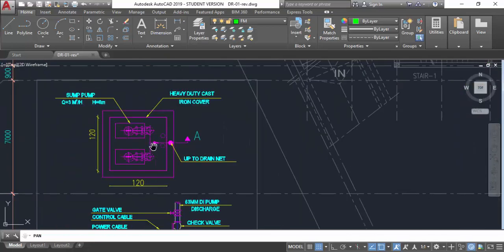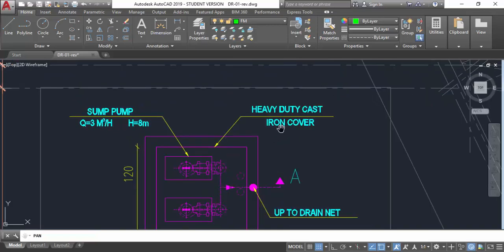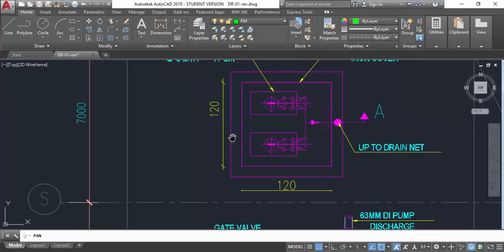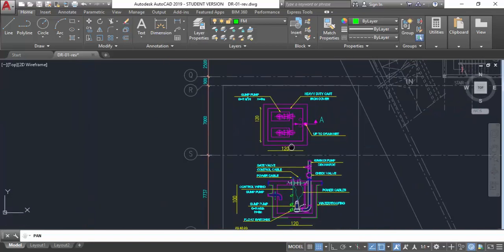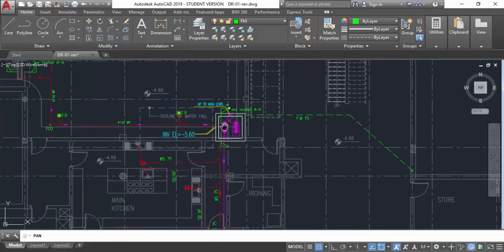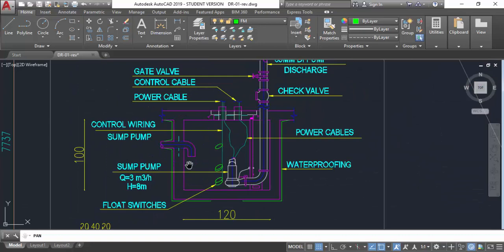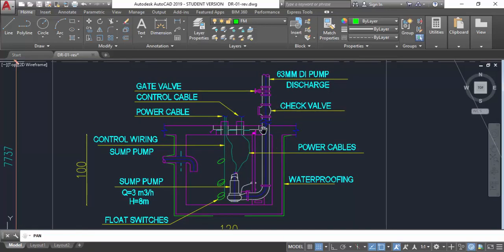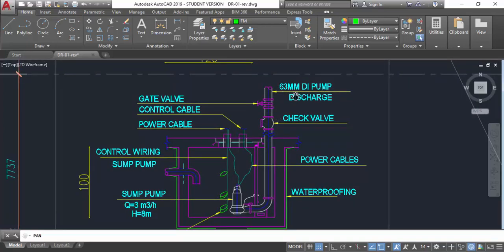In the section detail, you can see the sump pump installation. The pit dimensions are shown: 1.2 meters by 1.2 meters. The components include a power cable, floating switch, waterproofing, a check valve, and a gate valve. The check valve ensures water does not flow back. The pipe diameter is 63 mm. You also have a control cable going to the control panel and a power cable going to the pump. This is a heavy-duty pump as specified in the schedule.